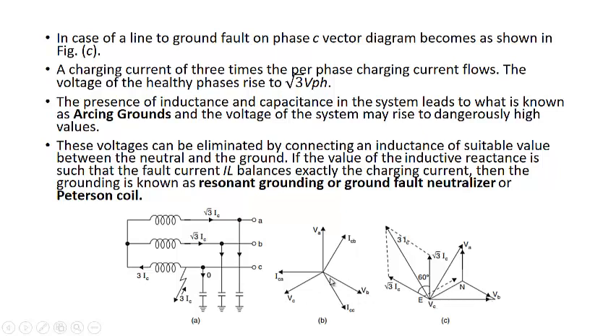Now the current, that is the capacitive current, we are assuming an unloaded system. The capacitive current in case of phase A will be with respect to VAC, that is with respect to this vector. This is the current between phase A and ground, and we have already seen that there will be a capacitance between phases and ground. This is the fictitious capacitor.